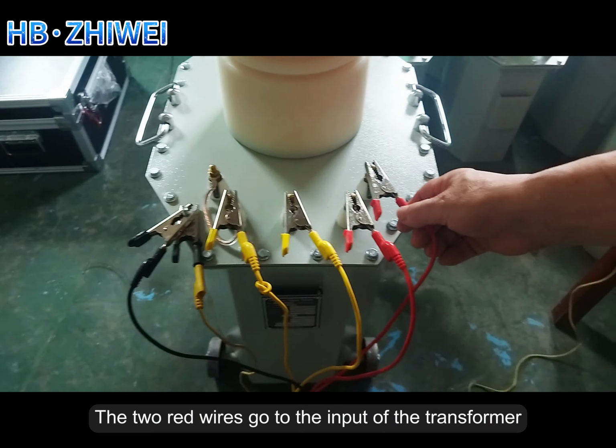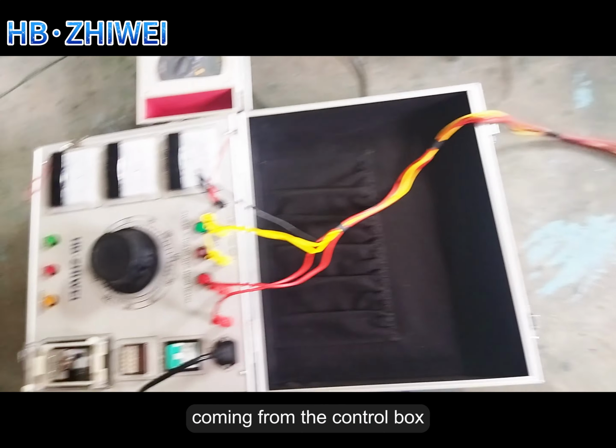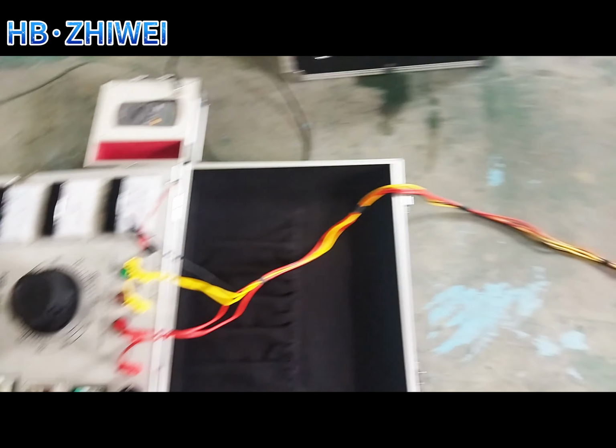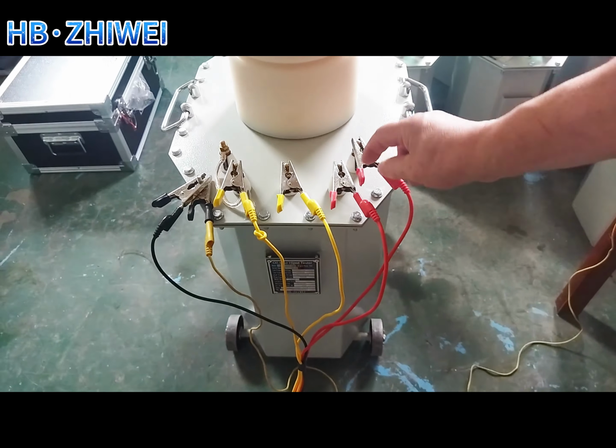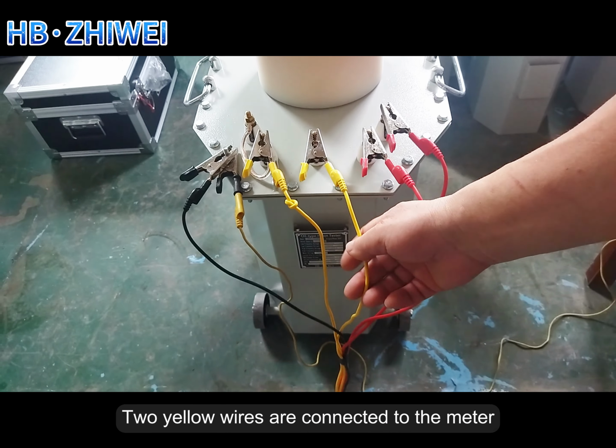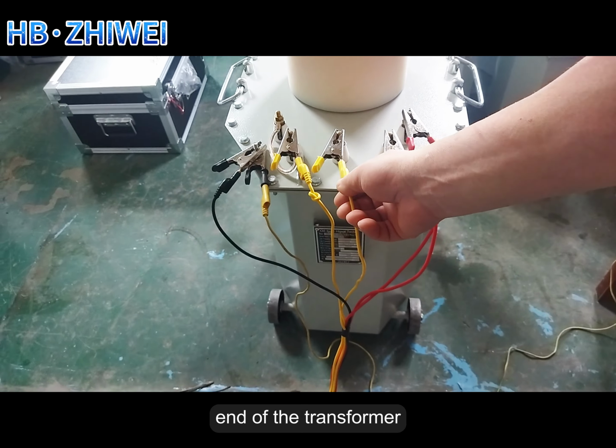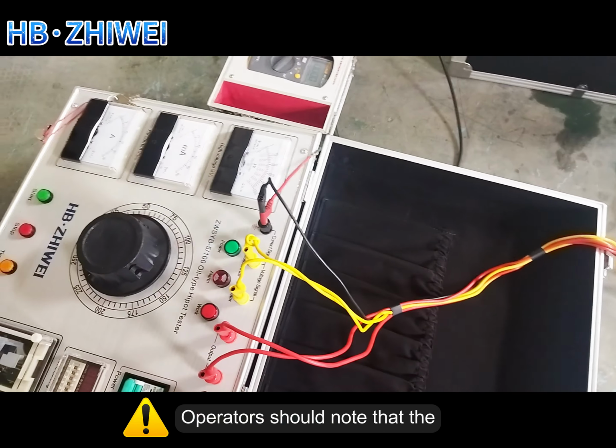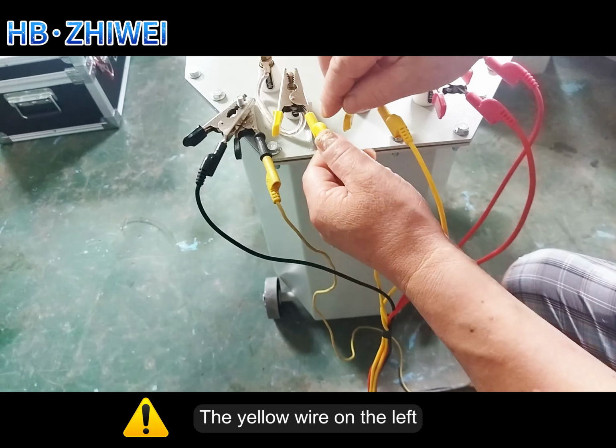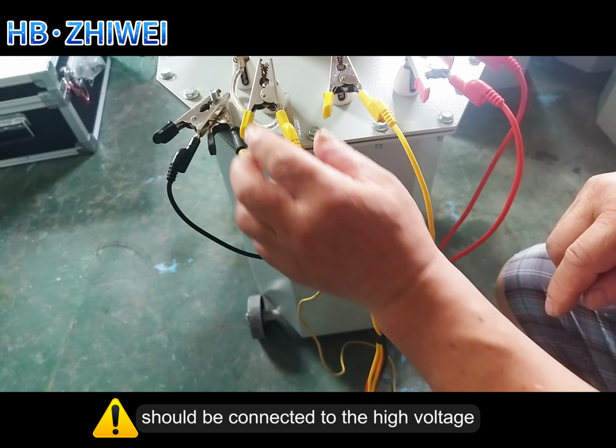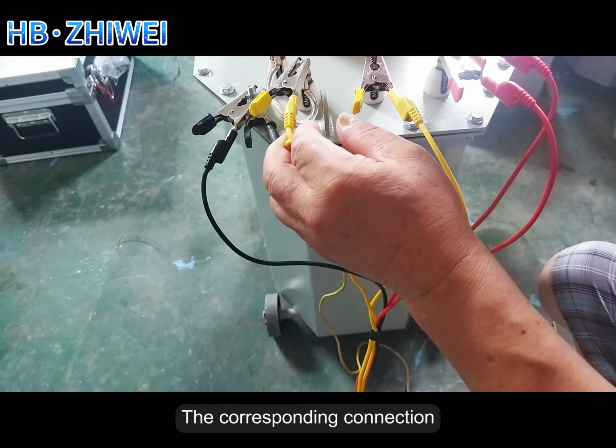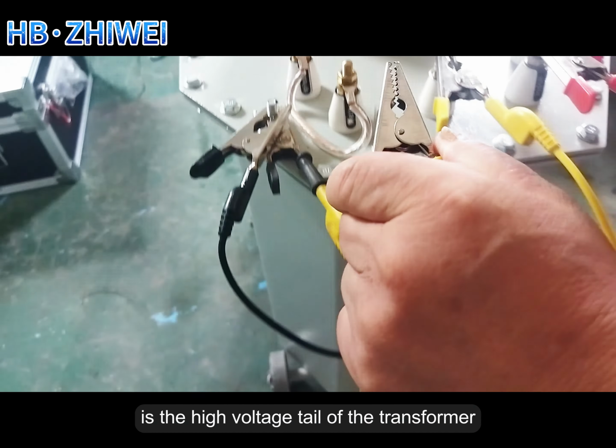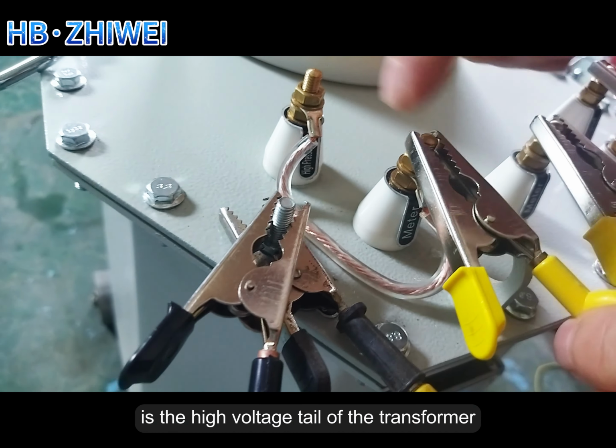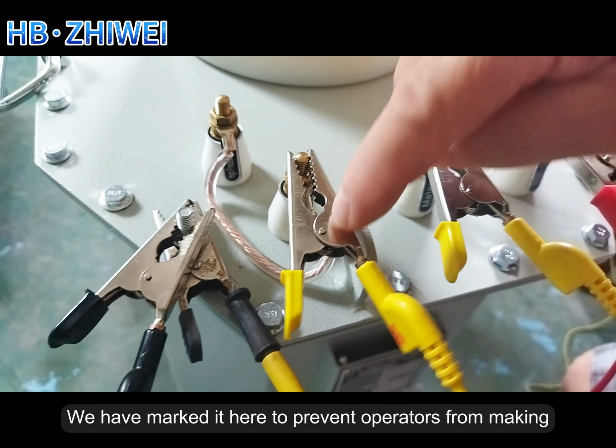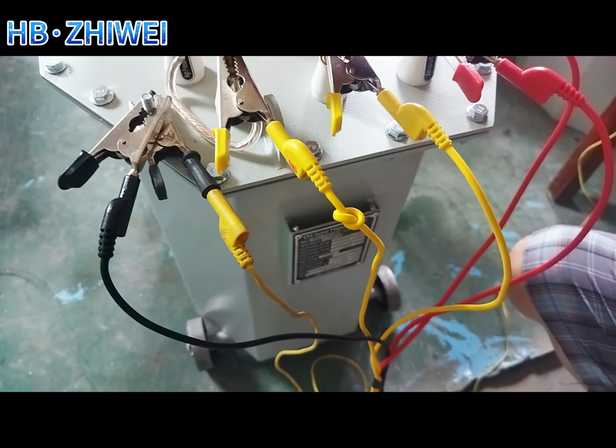The two red wires go to the input of the transformer coming from the control box. Two yellow wires are connected to the meter end of the transformer. Operators should note that the yellow wires cannot be connected arbitrarily. The yellow wire on the left should be connected to the high voltage pressure tail of the control box. The corresponding connection is the high voltage tail of the transformer. We have marked it here to prevent operators from making mistakes.